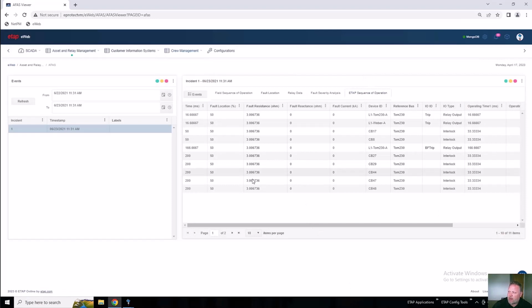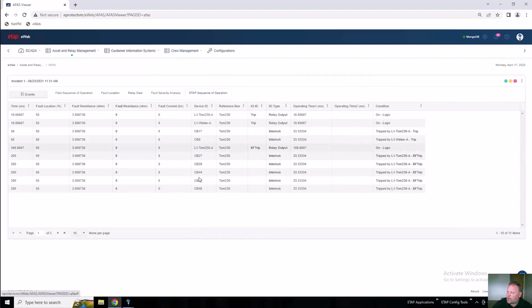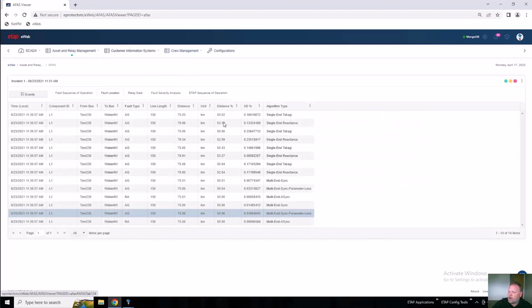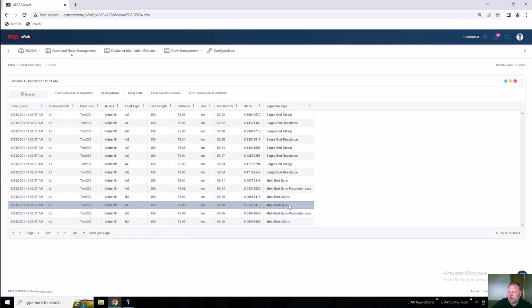So here, and let me hide my events here so we can see all the details. Here we break down, we actually take the fault, let me go back to the fault location here. We use the multi-ended synchronous results, which are the most accurate, if we have them, place that fault in the ETAP model, and run a star-Z protection coordination study, and find my sequence of operations as a result of this.